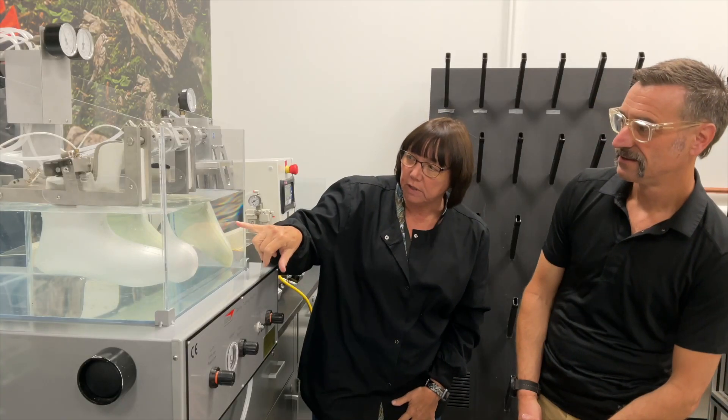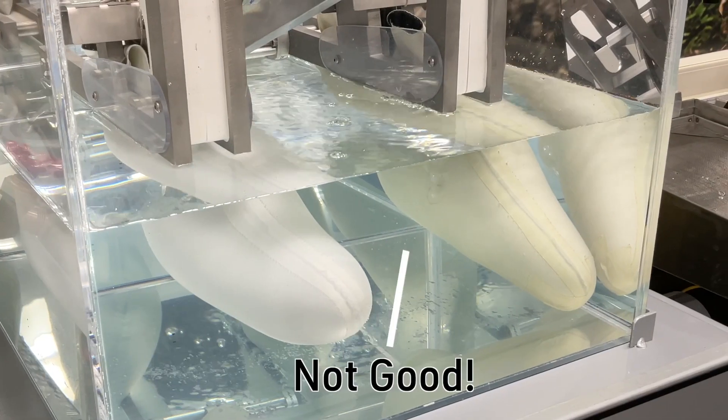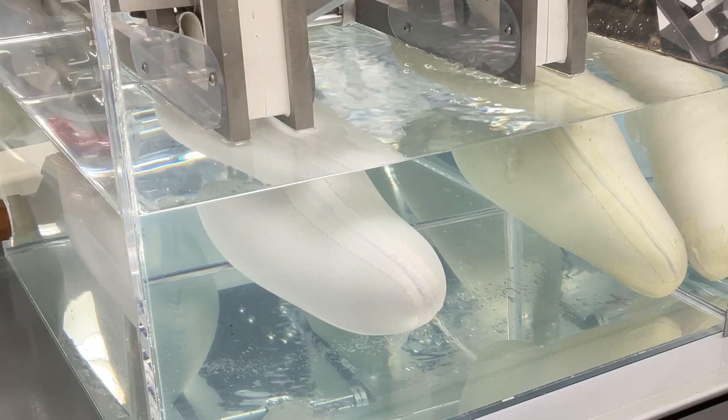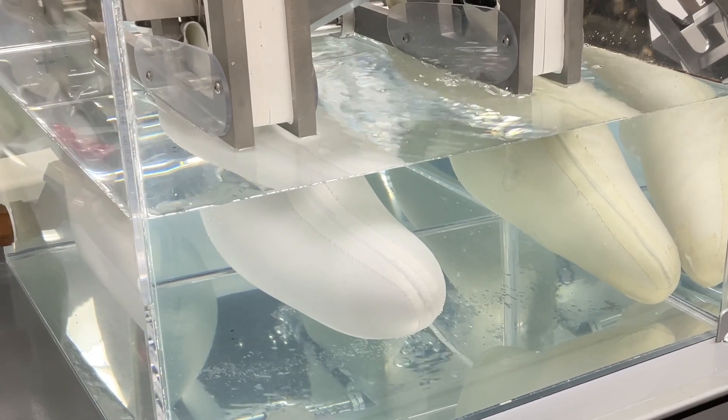I have a demo here to show you what a failure would look like. On this booty, you can see air coming out of a little hole — a rapid stream of air bubbles — so this would be a failure. On this other booty, you see some air bubbles but they're staying attached, so that would be a good booty.